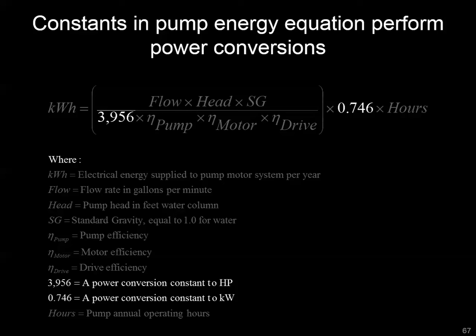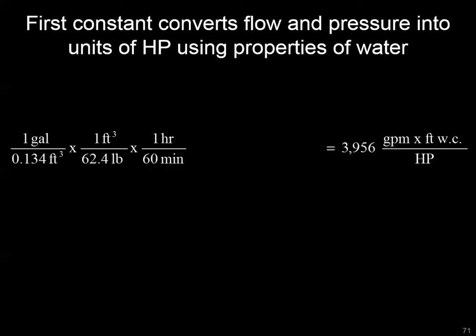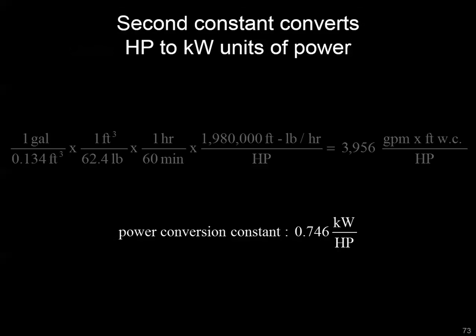There are a few constants to cover briefly. The first is 3956, which is a conversion between GPM and feet of water column to horsepower. It's derived from: a volumetric conversion (1 gallon = 0.134 cubic feet), a weight conversion for one cubic foot of water, a time conversion to use GPM, and a power conversion from foot-pounds per hour to horsepower. The second constant is simpler: 0.746, which is a straight conversion from horsepower to kilowatts.